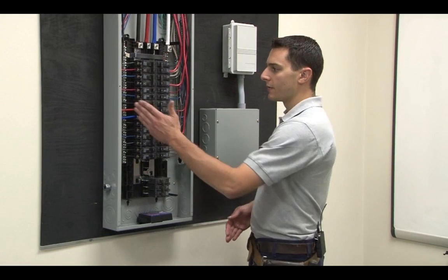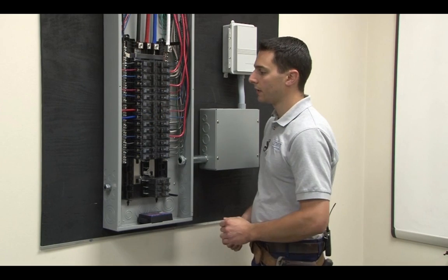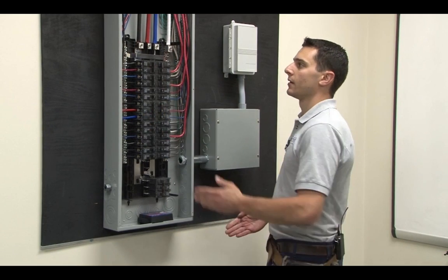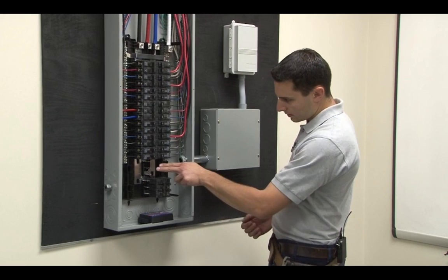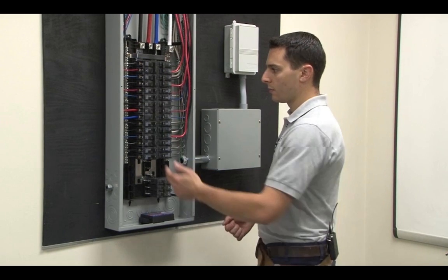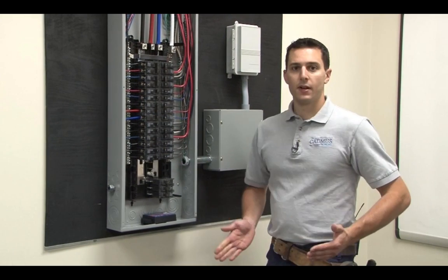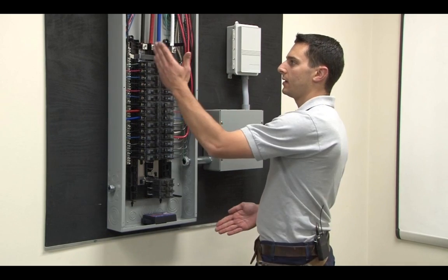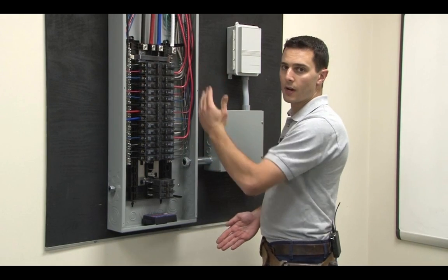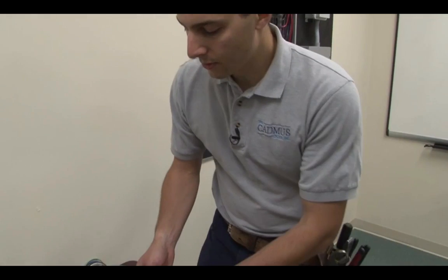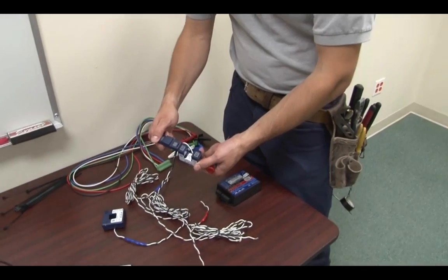We'll locate our CTs on these conductors for this 50-amp circuit, and our voltage leads can either go up here or down here, or if available, they can go on these conductors. These panel boards are wired phase A, B, and C, left to right, and top to bottom. We'll start by wiring our CTs to the Wattnode. We'll use a split-core current transformer. Again, these are directional.